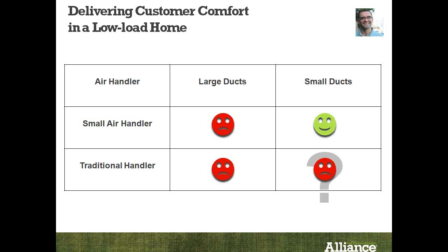So large ducts with a traditional air handler, let's say that's both a 5-ton air handler and a 5-ton duct design, it's going to short cycle so often in a low-load home that you aren't going to be able to ever remove the humidity, and the noise of the system starting up and shutting down is going to be a problem too. So we've noticed that if you have an air handler that's running for an hour and a half, people aren't going to notice the noise as much because they become somewhat numb to it, whereas if the system starts up and shuts down every 5 minutes, you're going to have a lot more complaints about it. And a traditional air handler with small ducts doesn't really make a whole bunch of sense.